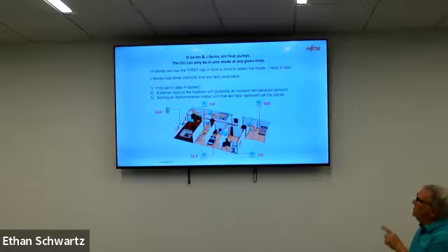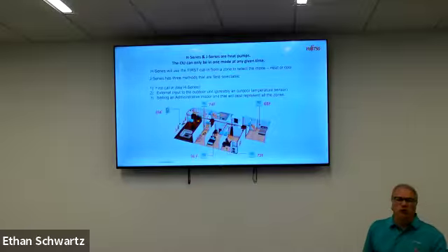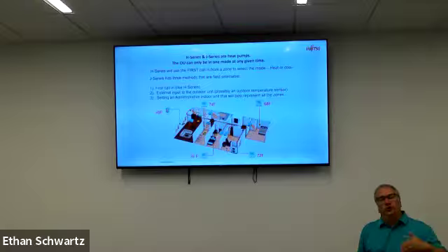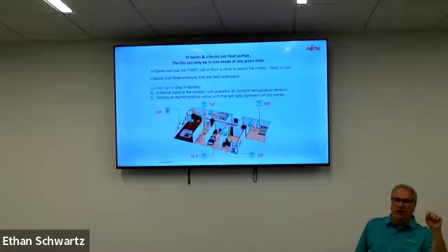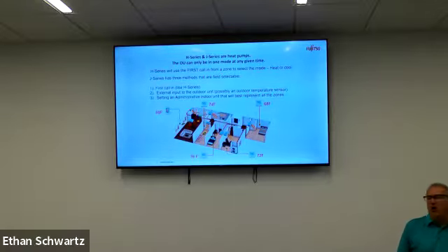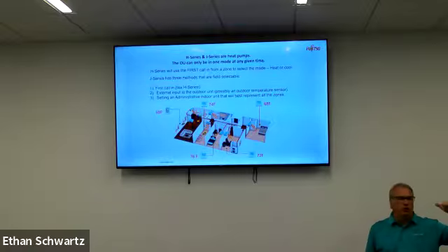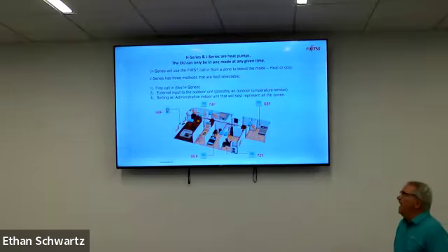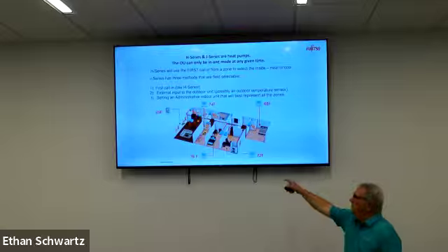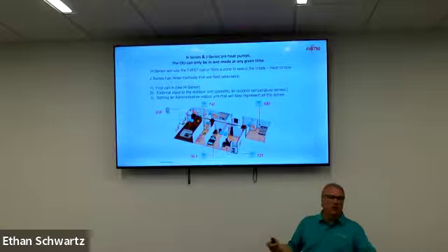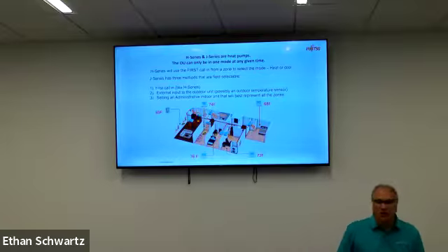The second is external input to an outdoor unit. So you can have a third party control, you need a connector kit. And if we know that a building needs to go into cooling when the temperature gets up to 48 degrees outside, well, then we set that up. And that sends a signal into the unit, and the unit stops and it changes mode.